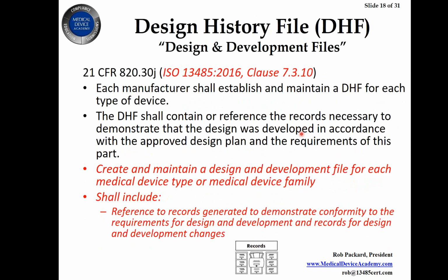And you don't actually have to have a binder per se. You don't have to have a big, thick 3-ring binder with all the documents in there and keep everything paper-based. You don't have to have an elaborate electronic control system where everything's software either. But you can have a design history file where it references all these control documents. So that is allowed, but it should follow your design plan. So whatever your plan says, that's what should be in the DHF.